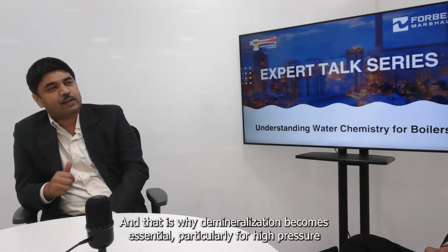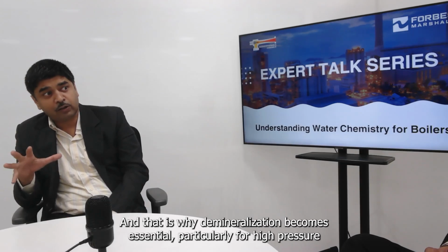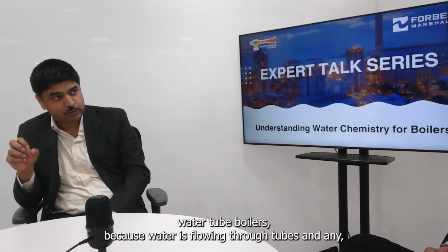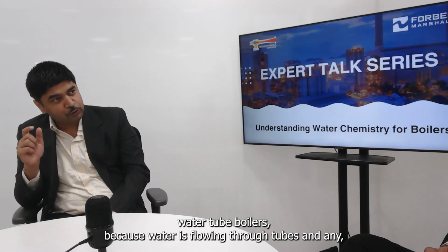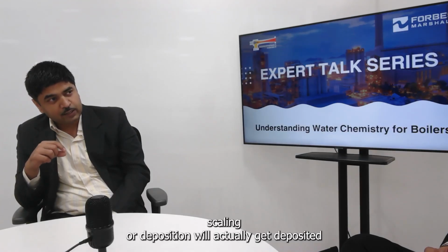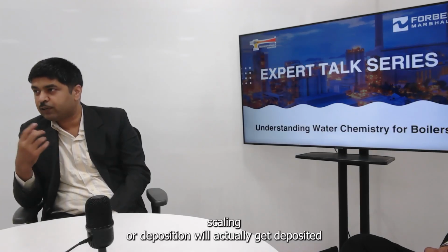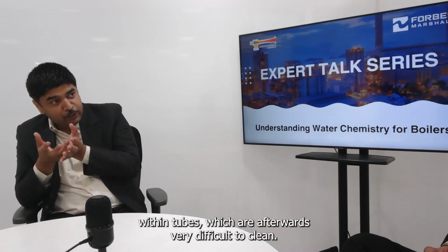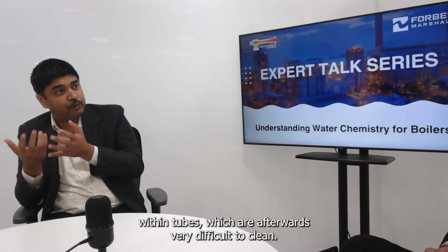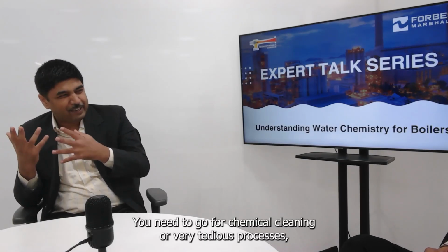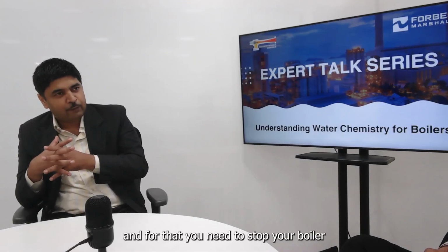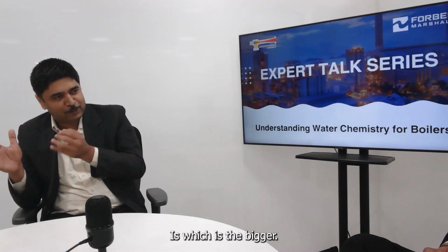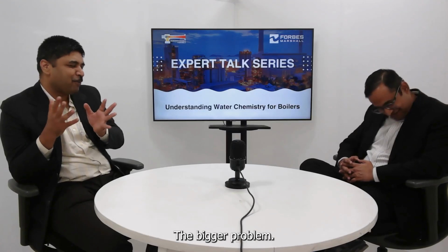And that's why demineralization becomes essential, particularly for high pressure water tube boilers. Because water is flowing through tubes, and any scaling or deposition will get deposited within the tubes, which is afterwards very difficult to clean. You need to go for chemical cleaning or very tedious processes. And for that you need to stop your plant, obviously. Which is a bigger problem.